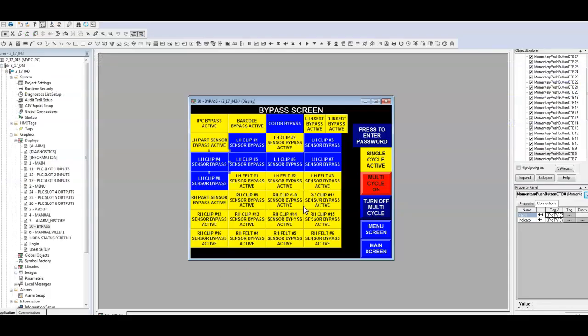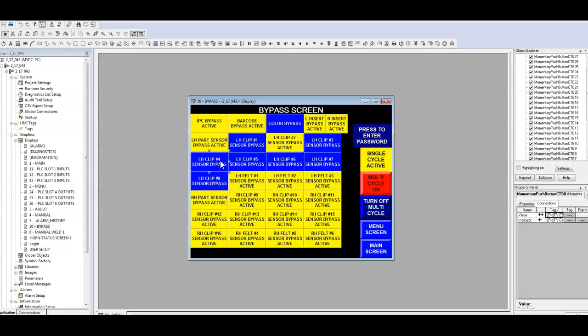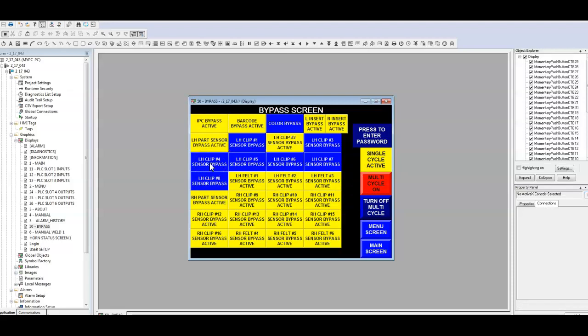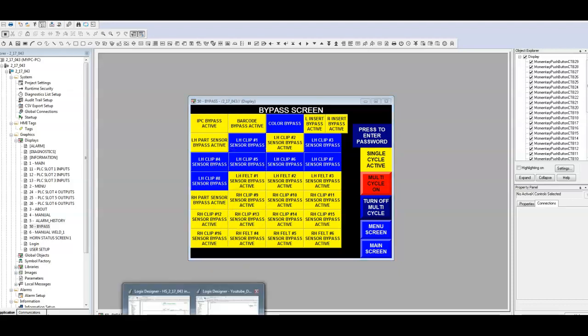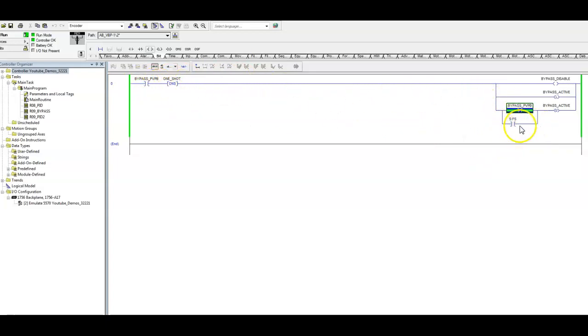And then the types of buttons that you would use. So in this particular case, this screen is packed. Now we could have multiple screens on here and have tons of different buttons. But what's chosen here is a momentary button, so that you can, if you recall, push and let go. So it's going to be energized just for a moment. So somehow we've got to latch that button closed. But then we're using a one-shot. So we're going to push that button and we're going to then release it. So this is going to be our status. So on the first scan, this instruction will unlatch this bit, which will ensure that this bit is not energized, the bypass active.